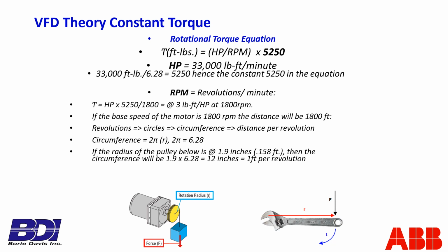Okay, so with that in mind, looking at this torque equation right here, torque equals horsepower times 5250 divided by RPM, a base speed 1800 RPM motor, that's where you put that value in. And if you divide that out, you get 5250 divided by 1800, that's approximately 3 foot-pounds per horsepower at 1800 RPM. Okay, and that power rating is the rating at the base speed of the motor, and the torque rating is the torque rating at the base speed of the motor.